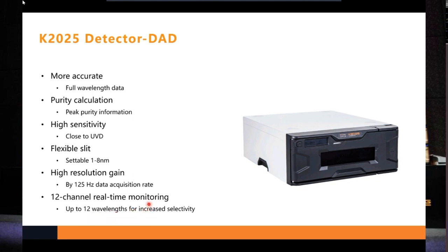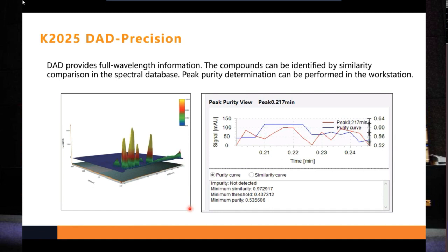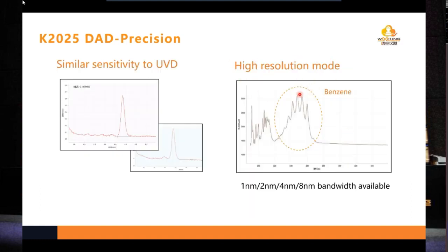Monitoring channels can be used during the running of samples. DAD provides full wavelength information. The compounds can be identified by similarity comparison in the spectral database. Peak purity determination also can be performed in the workstation when using DAD. The right picture here shows a high resolution mode by choosing the suitable bandwidth. We can choose 1 nanometer, 2 nanometer, 4, and 8 nanometers when needed.